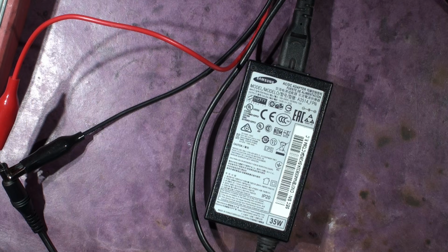If I put the current up now, we've got 200 milliamps, now we've got 7 volts. 600 milliamps, 7 volts. An amp is 6.9 volts, 1.3 amps, and it drops right down to 1.2 volts. So it's producing some power, but not at 14 volts. It seems the voltage is all completely wrong. It's very strange actually. So either there's something strange going on - some advanced function which makes the monitor call for more power, some communications down one of the power lines, which is very unlikely - or it's just a faulty power supply.